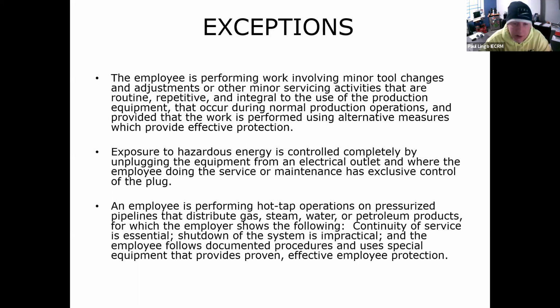So I would start with labeling. That's the first administrative control we need to pay attention to - what is our designation or identification of our energy, whether electrical, mechanical, or pneumatic. We need to identify not just what it is, but where the energy is coming from. If we're doing de-energization correctly, you only have to don that PPE one time, and you can ensure downstream of that energy through selective coordination and everything like that.